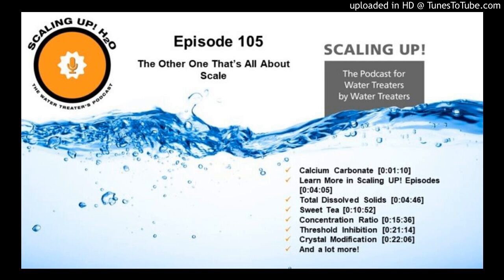The next thing that we might use is crystal modification. Now, folks, if you have ever seen an electron scanning microscope picture of calcium carbonate, it is really cool. It is a perfect square. And what do squares do? What do boxes do? They stack very well. That's why we can scale up a system overnight, and it takes so long for us to clean it up. It packs in there so tight because of the way that that crystal grows.